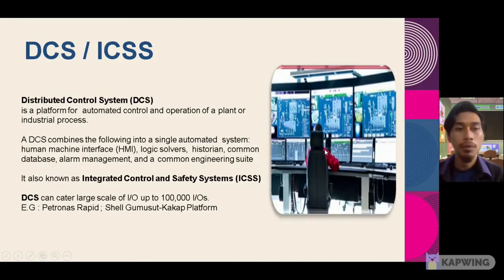Today I will explain about distributed control system or DCS. DCS is a platform for automated control and operation of a plant or industrial process. The DCS combines the following into a single automated system: human machine interface, that is HMI, logic solvers, historian, common database, alarm management and a common engineering suite. It's also known as Integrated Control and Safety System, ICSS. DCS can cater to a large scale of I/O, up to 100,000 I/Os. Example, Petronas Rapid, Shell Gumusut-Kakap platform.